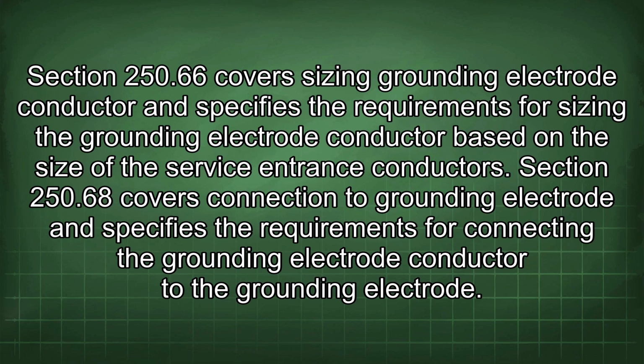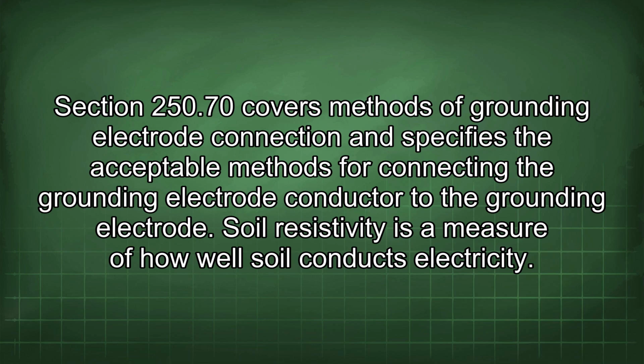Section 250.66 covers sizing grounding electrode conductor and specifies the requirements for sizing the grounding electrode conductor based on the size of the service entrance conductors. Section 250.68 covers connection to grounding electrode and specifies the requirements for connecting the grounding electrode conductor to the grounding electrode. Section 250.70 covers methods of grounding electrode connection and specifies the acceptable methods for connecting the grounding electrode conductor to the grounding electrode.